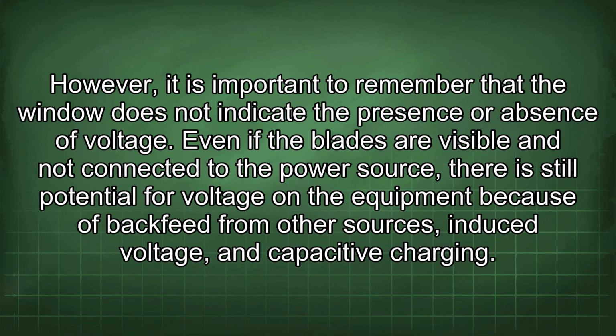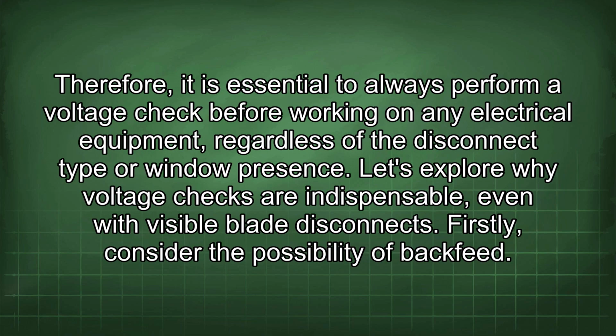Even if the blades are visible and not connected to the power source, there is still potential for voltage on the equipment because of backfeed from other sources, induced voltage, and capacitive charging. Therefore, it is essential to always perform a voltage check before working on any electrical equipment, regardless of the disconnect type or window presence. Let's explore why voltage checks are indispensable, even with visible blade disconnects.